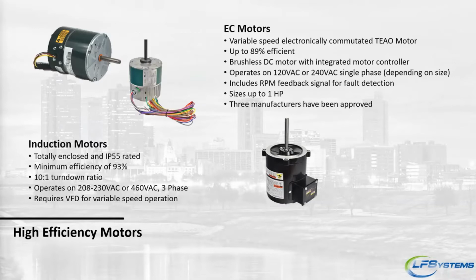Anything above that, if we start getting above about 2,500 CFM, we go to our 3-phase induction motors. And these are standard off the shelf, normal frame motors. There's nothing custom or special about these. But these actually give us a 10-to-1 turn down, so we'll turn down to about 6 hertz. And we can do either 230 or 460. Also, if you're in Canada, we do offer 575 volt 3-phase as an option.